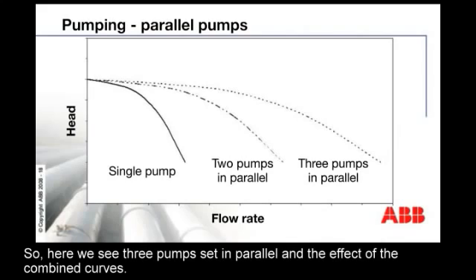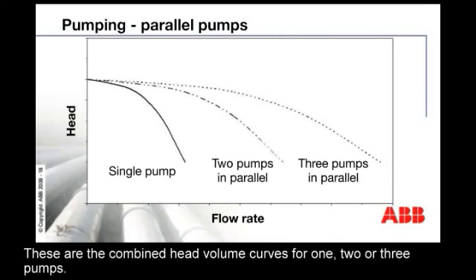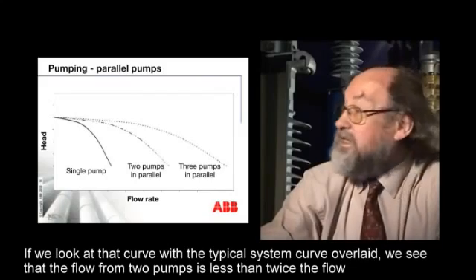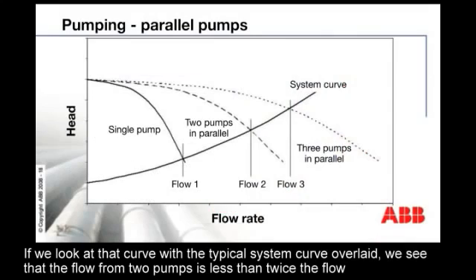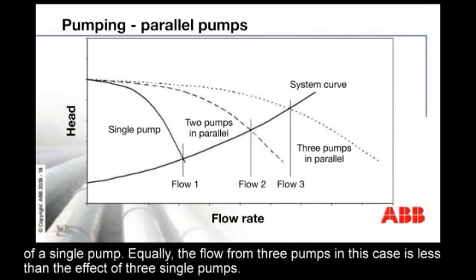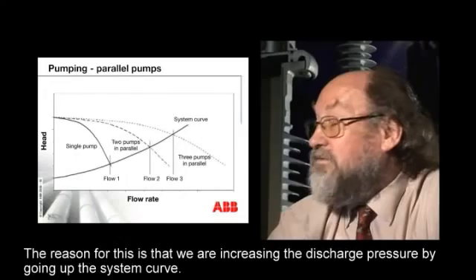Here we see three pumps set in parallel and the effect of the combined curves. These are the combined head-volume curves for one, two, or three pumps. If we look at that curve with a typical system curve overlaid, you'll see that the flow from two pumps is less than twice the flow of a single pump.